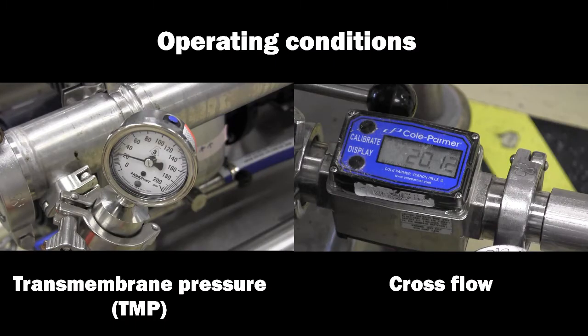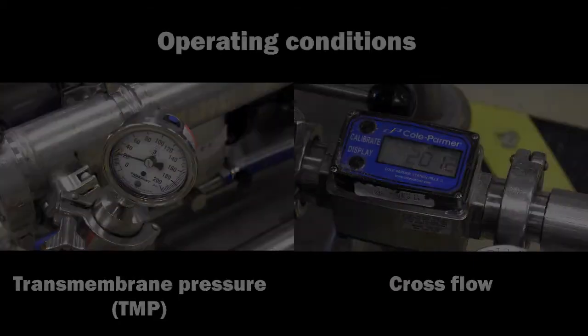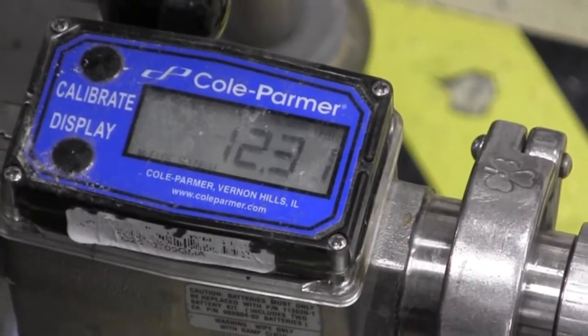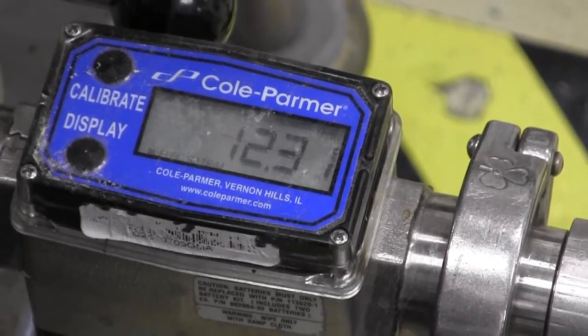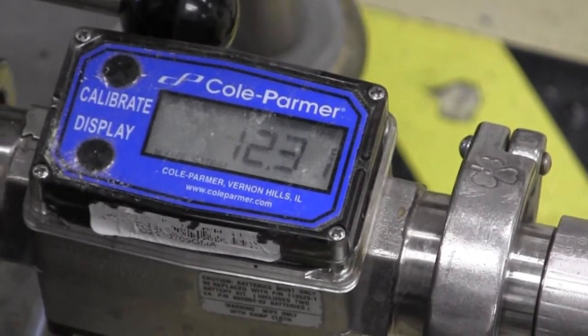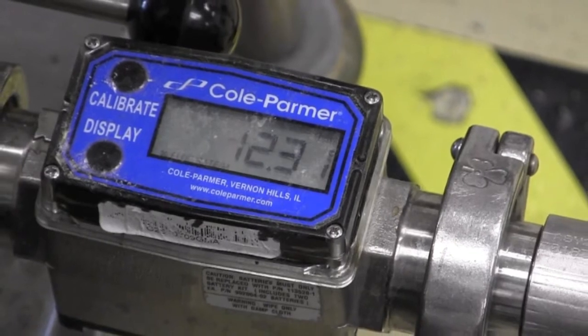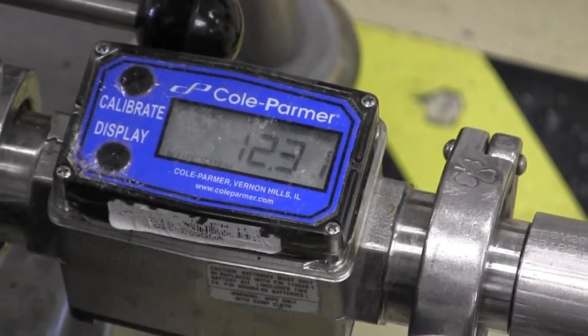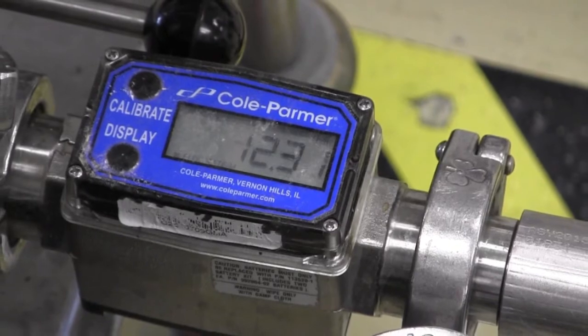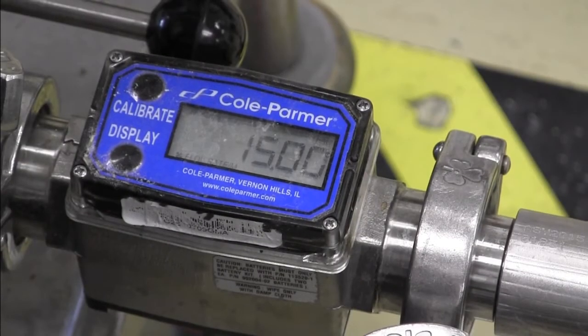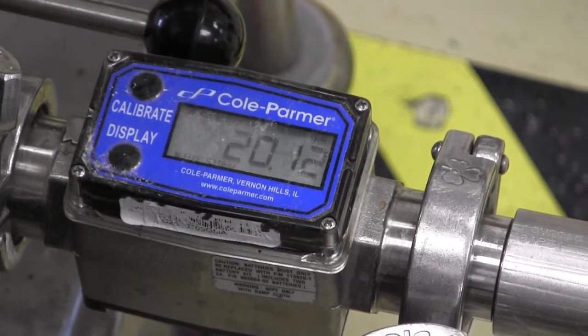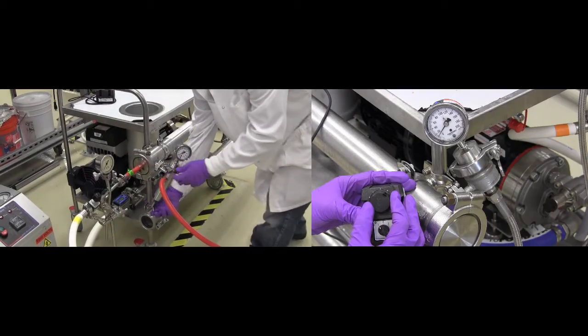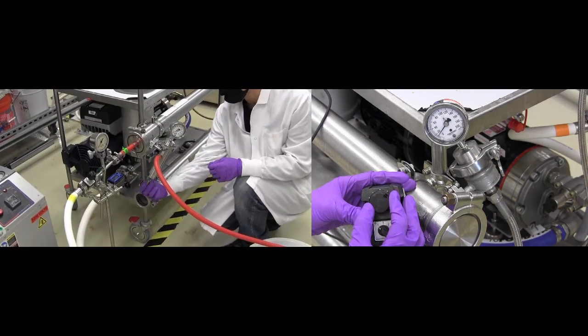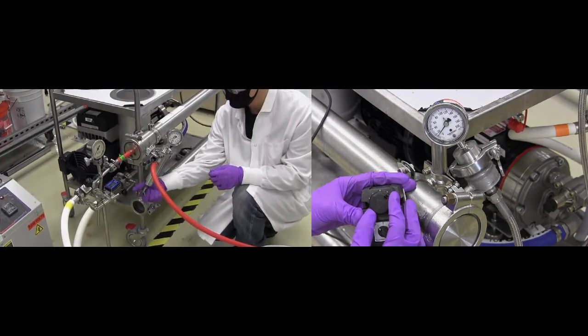In general, the goal is to maximize the TMP with a sufficient crossflow rate to prevent premature fouling of the membrane. For instance, running the system with a very high TMP but relatively low crossflow will result in initially high flux that quickly degrades as the membrane pores are overwhelmed with accumulated particulates. A more conservative approach is to start with a high crossflow rate and a low TMP. As the process is monitored, the TMP can be gradually increased.